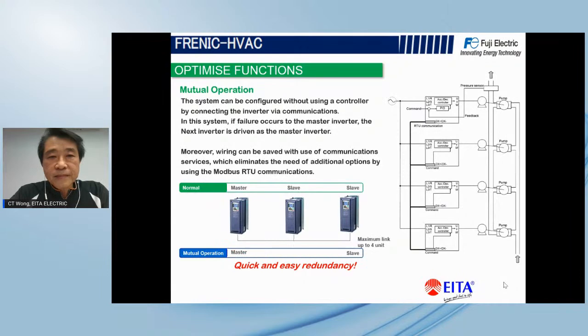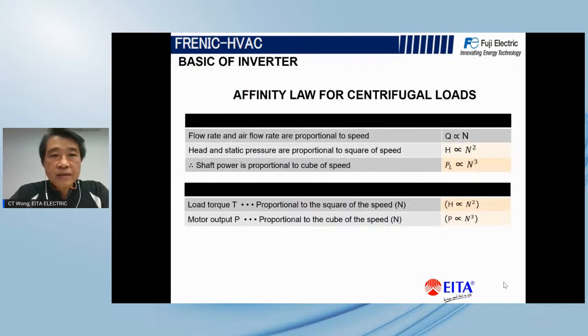Let's see. Well, let us look into the energy saving based on the affinity law. We just concentrate on this: the motor output is proportional to the cube of the flow. So that is the affinity law for the centrifugal load. Please remember this formula.